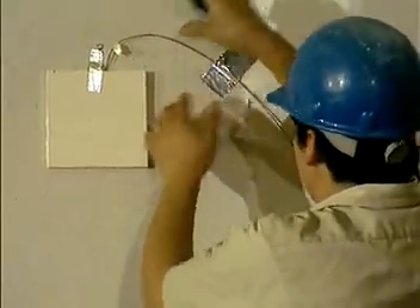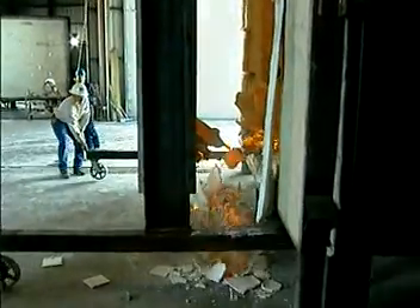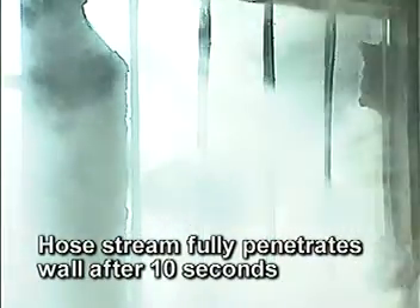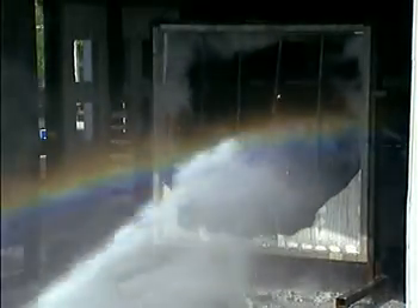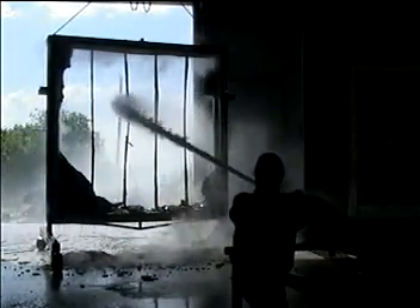This is what's left of a two-hour fire-rated sheetrock wall. The ASTM E119 test is then repeated on high-impact gypsum. Many building materials are classified as fire resistive, meaning they will burn if they get hot enough. These materials may be fire rated for one or two hours, but as you will see, that designation can be very misleading.